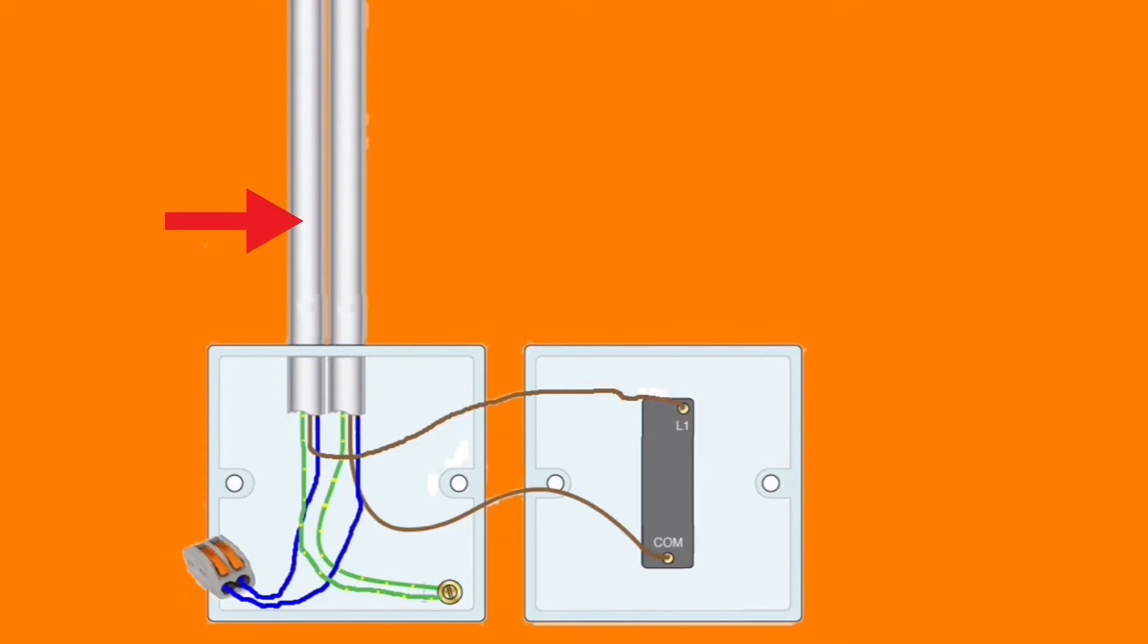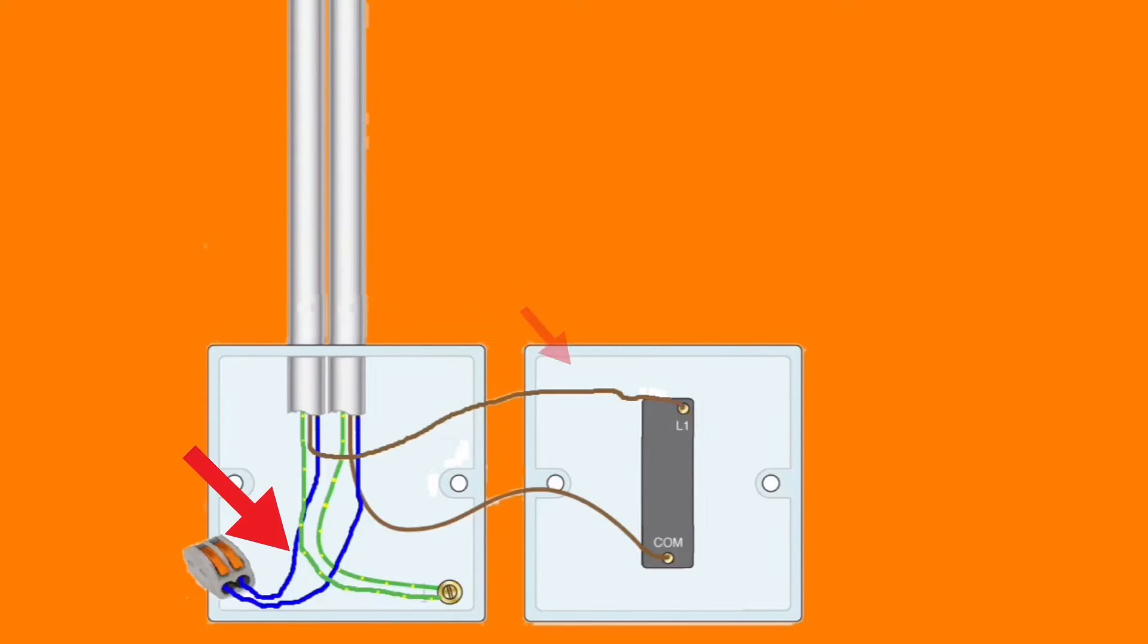The cable going out that will feed the lighting points has the brown switching line conductor connected in L1, its blue conductor which is a neutral connected with the other neutral from the supply in this case in the maintenance-free connector block, and the CPC secured also with the other CPCs in the earth terminal itself.